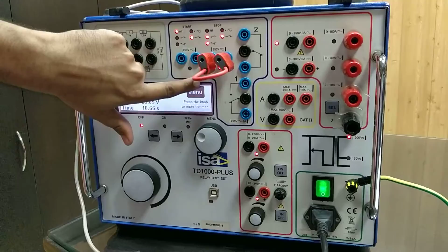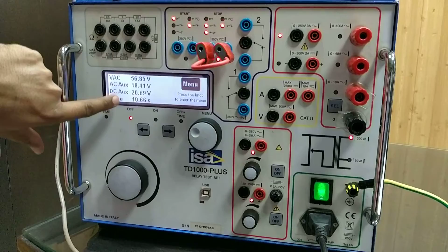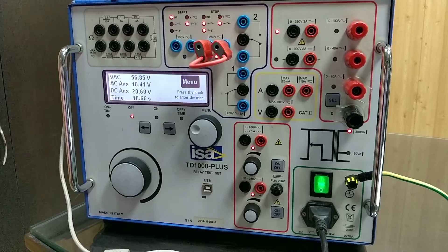And now we are manually short circuiting the stop contact to measure the trip time, and once the stop contact is closed, the LED will be glowing, and you can see on the screen it is showing the exact delay from the starting of the generation up to the tripping of the relay.